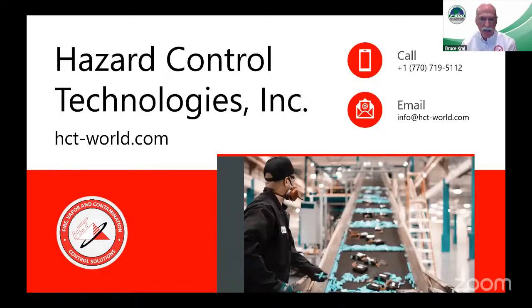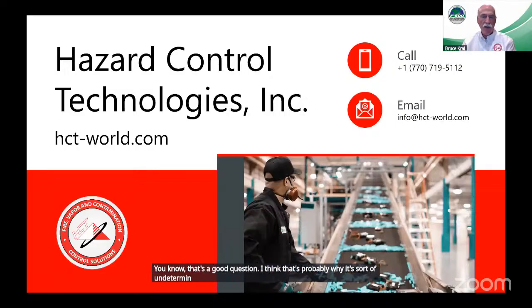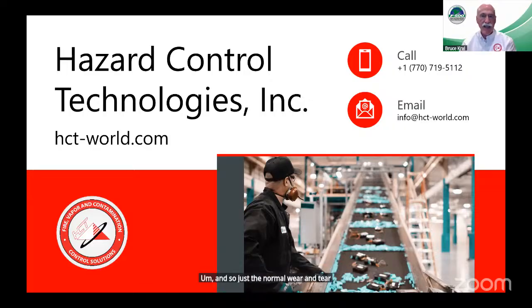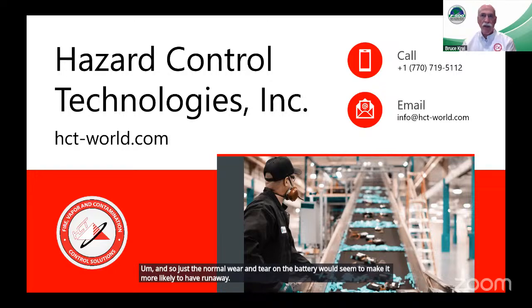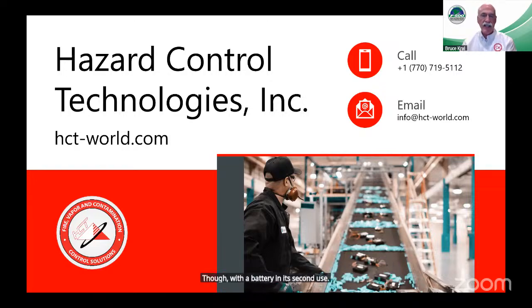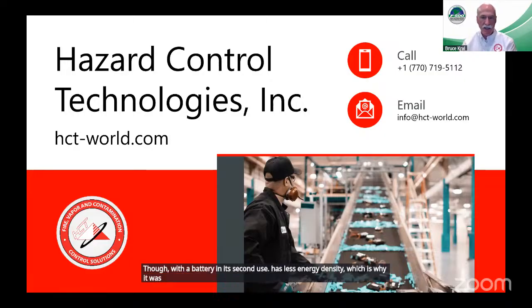Do second life batteries have a higher chance of runaway versus first life? That's a good question. I think that's probably why it's sort of undetermined at this point. You can imagine that second life batteries have been handled more. They've been installed, used, and then removed and transported. So just the normal wear and tear on the battery would seem to make it more likely to have a runaway. Though, with a battery in its second use, has less energy density, which is why it was taken out of service. So the amount of power inside the battery, if and when it fails, is somewhat less. So somewhere in the balance, maybe it's more likely to fail, but the failure might be less dramatic.